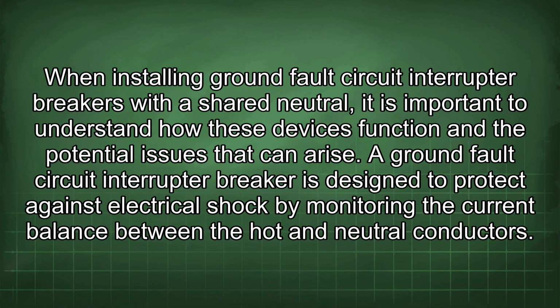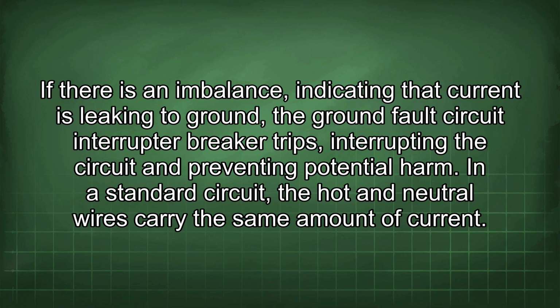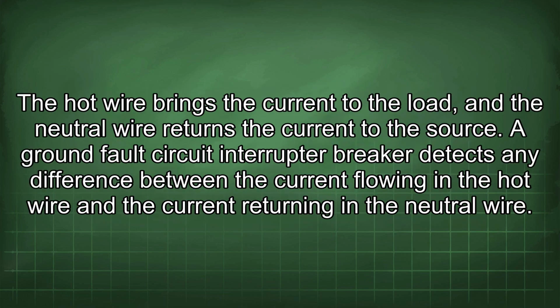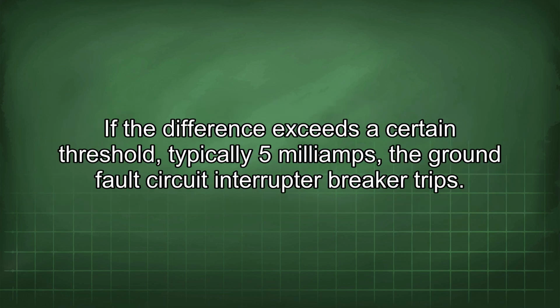A ground fault circuit interrupter breaker is designed to protect against electrical shock by monitoring the current balance between the hot and neutral conductors. If there's an imbalance, indicating that current is leaking to ground, the ground fault circuit interrupter breaker trips, interrupting the circuit and preventing potential harm. In a standard circuit, the hot and neutral wires carry the same amount of current. The hot wire brings the current to the load, and the neutral wire returns the current to the source. A ground fault circuit interrupter breaker detects any difference between the current flowing in the hot wire and the current returning in a neutral wire. If the difference exceeds a certain threshold, typically 5 milliamps, the ground fault circuit interrupter breaker trips.